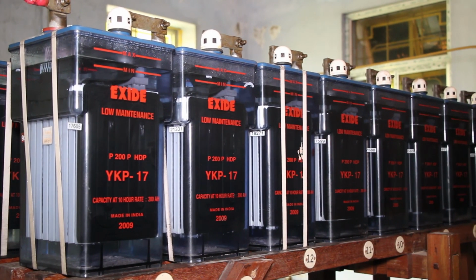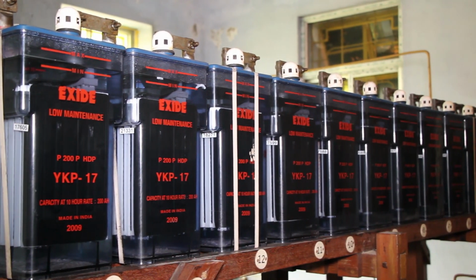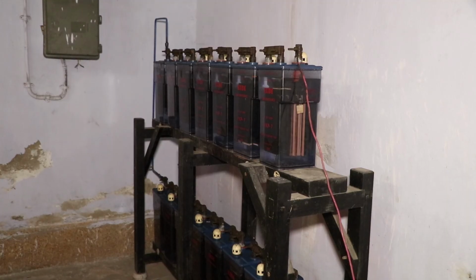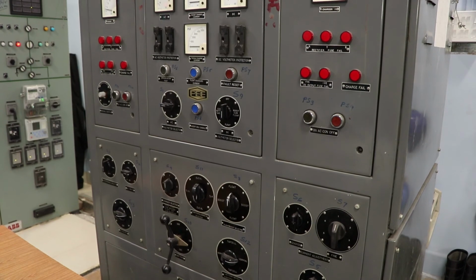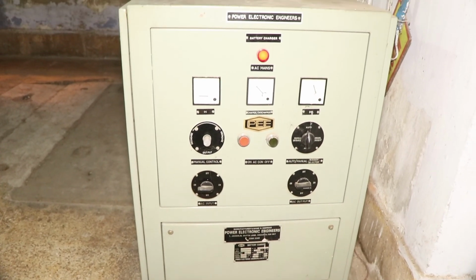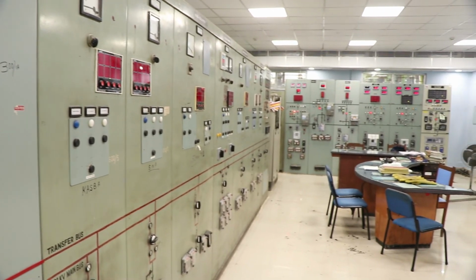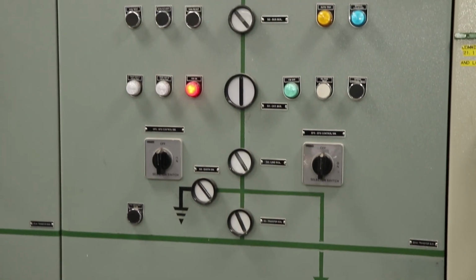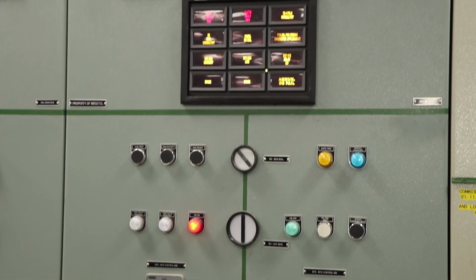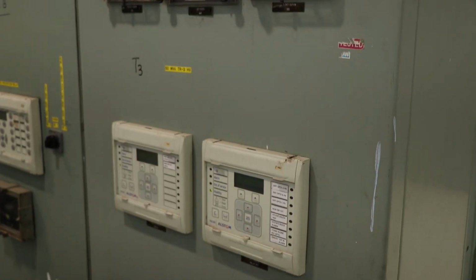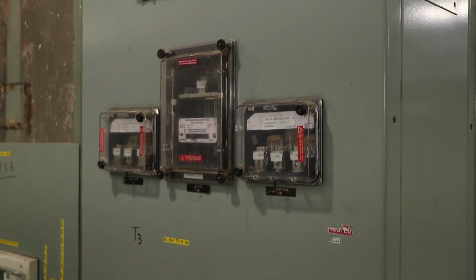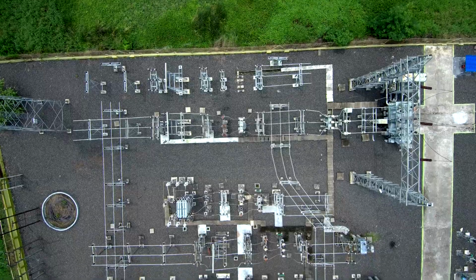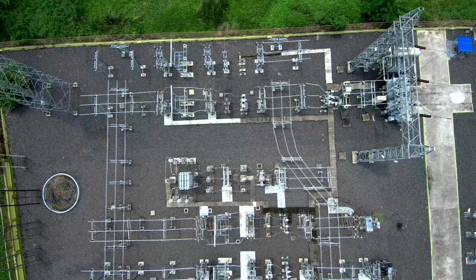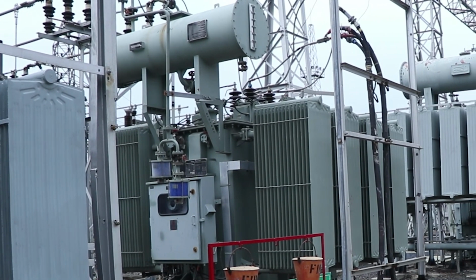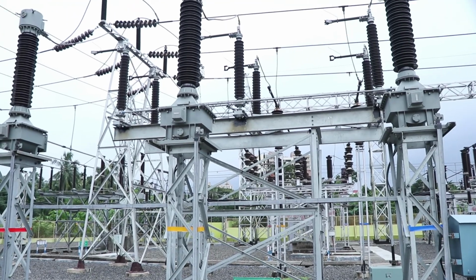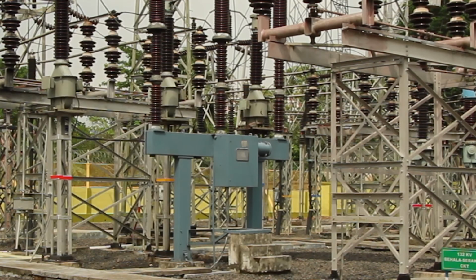For control panel DC supply, we have well maintained 220V DC and 30V DC battery banks through 220V DC and 30V DC battery chargers. For improvement and reliability of the system, we are replacing the old control panel with a new one. For better system protection, we are using numerical relays and many static relays. To improve quality of power transmission, many new projects have been taken up in the substation. Installation of new power transformer, installation of new CTs, PTs, breakers, isolators, etc.